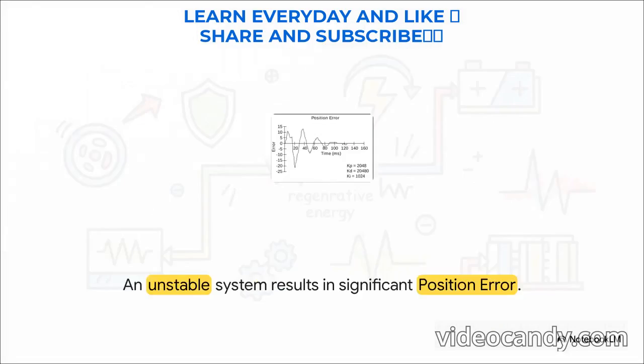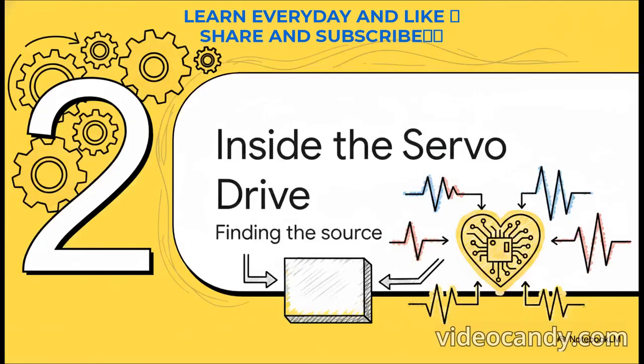And wow, this graph shows you exactly what happens when that law gets broken. Look at this. This is the position error of a machine with an unstable DC bus. All this chaos, these wild spikes and dips, it means the machine is literally not where it's supposed to be. It's getting commands, but it can't follow them because its power source is just all over the map.